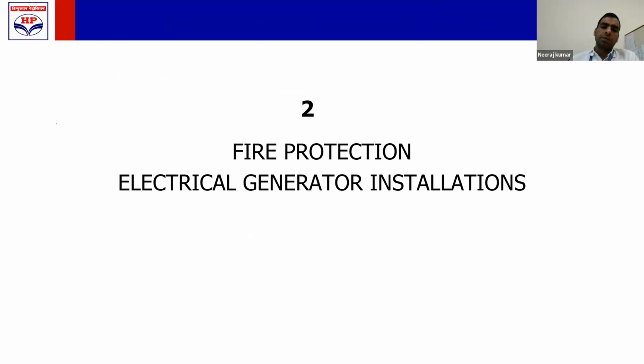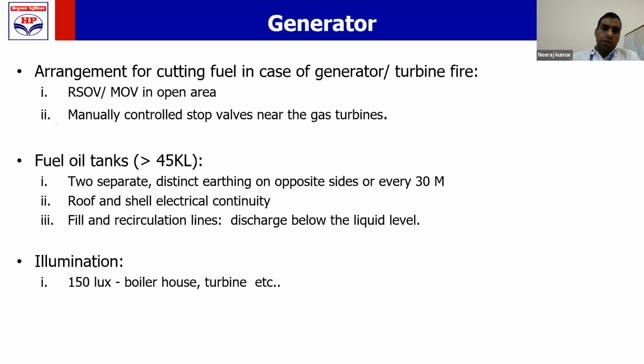Now we will discuss fire protection for generating installations. This section will have two parts: fire protection for gas turbine generators, or your main generators, and fire protection for emergency diesel generator. Let us see what the requirements are for your main generator. That will generally be a gas turbine, which may also have naphtha or diesel as fuel.